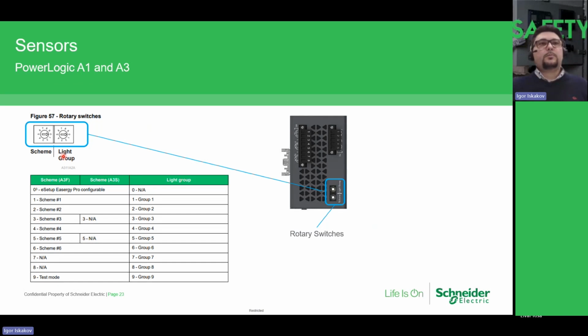Here you see how you can configure these devices. You have one DIP switch which chooses the curve. You can choose a different curve, which you can also find in more detail in the manual, and you can use the light group. For a big system, like the typical 20 kilovolt substation I described before, you will need at least 2 groups. For more complicated systems, with generators, motors and other systems, you can use more groups, using the light group for separation to have selective arc flash protection for your application.